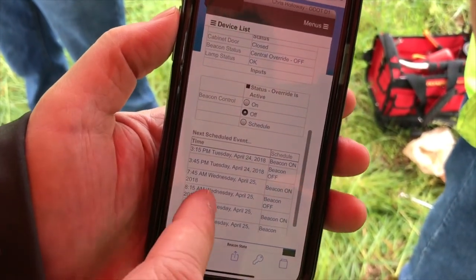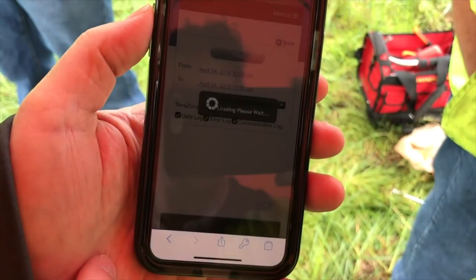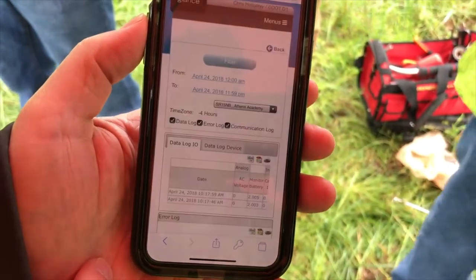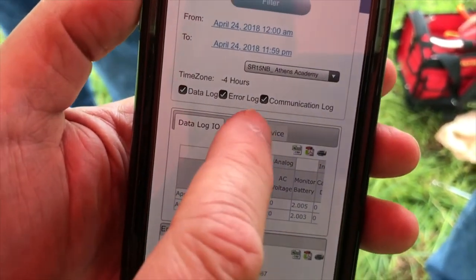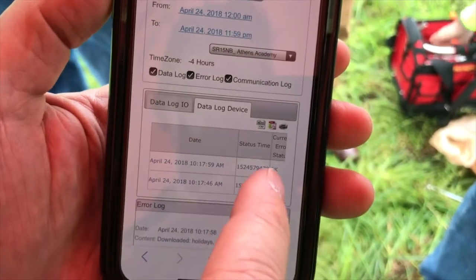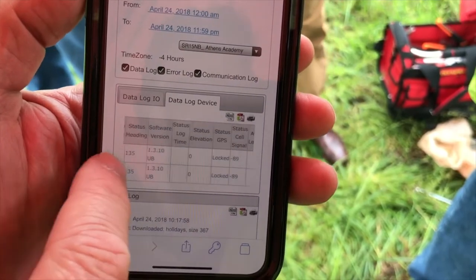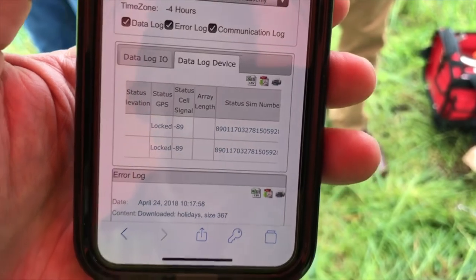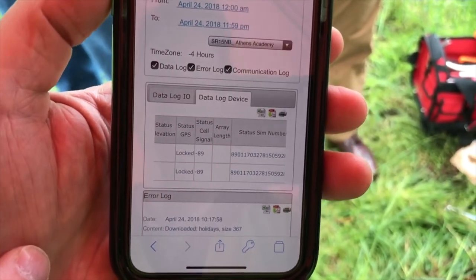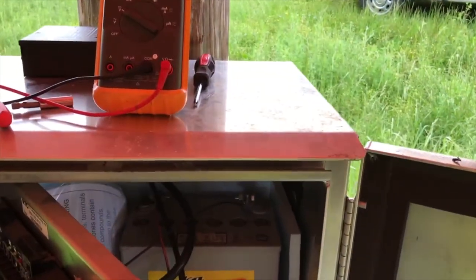Next we're going to look at the information under more details for the cell signal strength. This opens up the log of the data — there are two options: data log IO or data log device. Scrolling to the right will show us the cell signal strength, which is minus 89. On a 4G beacon, anything over minus 120 is good. So now we know we can install the antenna on top of that cabinet where we had it before.